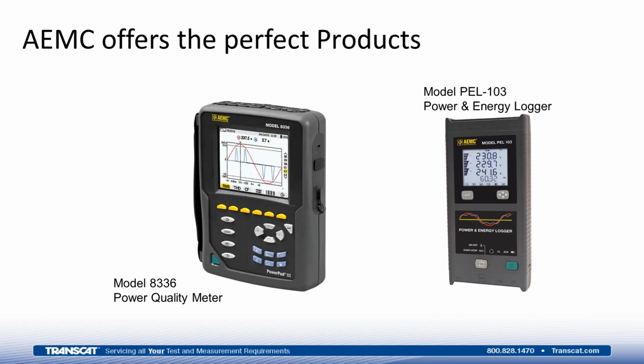AEMC does produce a couple products that are capable of doing this, and while this is not intended to be sales, this is intended to be a technical presentation, I just want to give you a look at a couple of the products. The product on the left is referred to as a PowerPad. It's a model 8336. It brings in all three voltages, including neutral and ground voltage connections, as well as four currents, the three phase currents plus the neutral current, and does what is referred to as a power quality study.